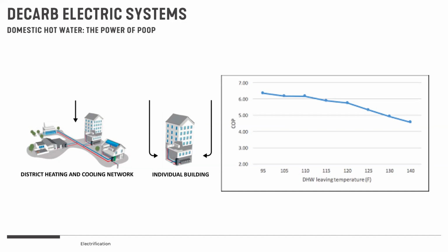The power of a heat pump pulling from a rich source like wastewater is that there's a lot of heat there to steal. So the efficiency of the heat pump goes up dramatically. These systems can actually produce 5 times as much heat as the actual electricity being used to power the heat pump.